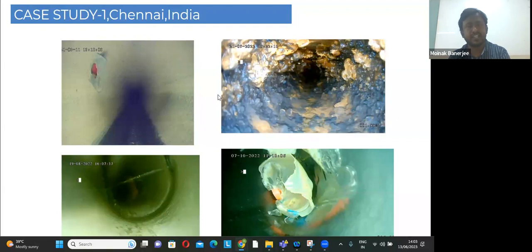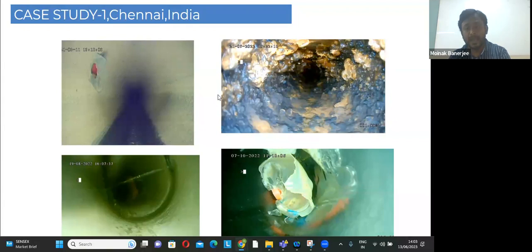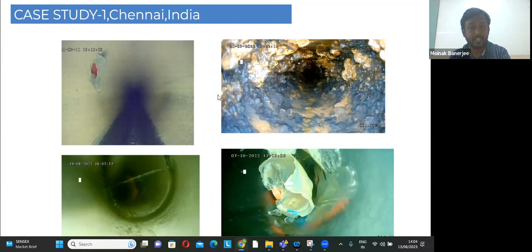The fourth major problem in Chennai is blockages. One of the major reasons for intermittent supply in India is blockages in pipelines — bottles, napkins, or other objects that somehow enter the water network and fully block flow pathways. This creates huge pressure differences causing ruptures and breakages. The robot application for finding potential blockages and pinpointing them allows right actionable rehabilitation to be implemented on specific points rather than making changes across the overall network.